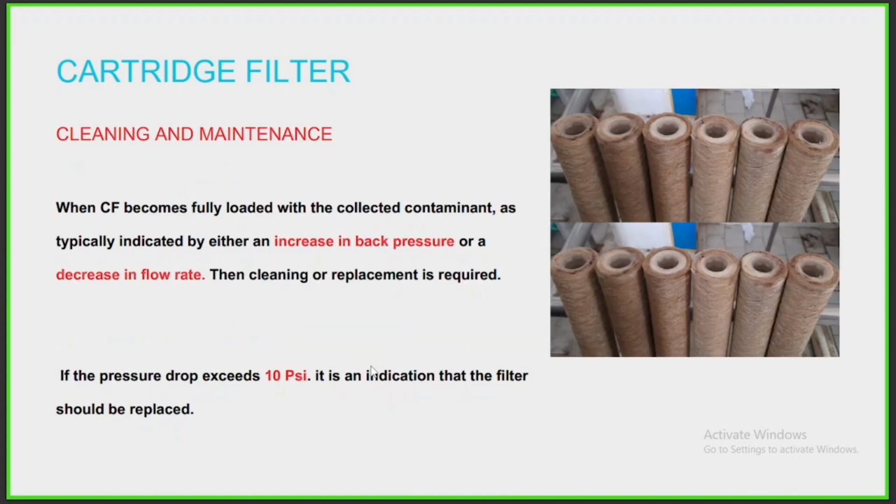Cleaning and maintenance. When cartridge filter becomes fully loaded with the collected contaminants, as typically indicated by either an increase in back pressure or a decrease in flow rate, then cleaning or replacement is required. If the pressure drop exceeds 10 psi, it is an indication that the filter should be replaced with a new one.